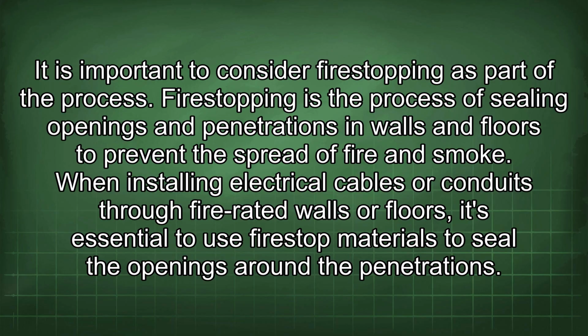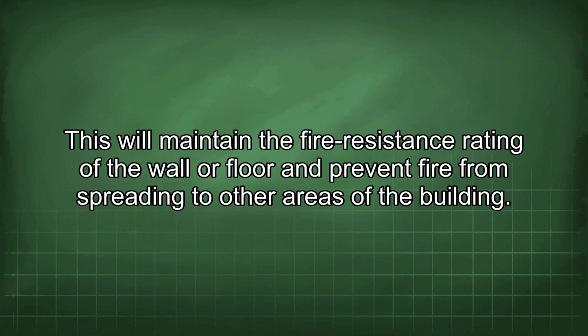Fire stopping is the process of sealing openings and penetrations in walls and floors to prevent the spread of fire and smoke. When installing electrical cables or conduits through fire-rated walls or floors, it's essential to use fire-stop materials to seal the openings around the penetrations.